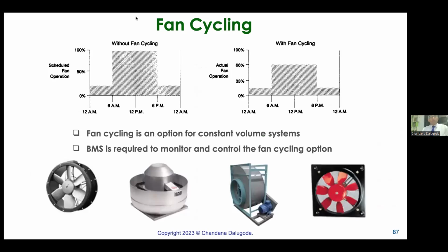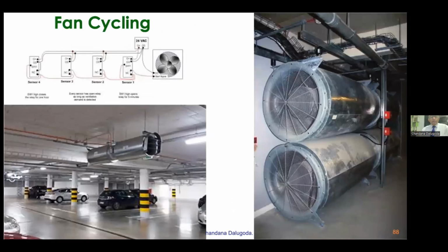Next one is fan cycling. Now fans are working continuously, at full load. That is energy killing. Say when 100% working, when it is reduced at part loads, that is fan cycling. The fans used in car parks, fan cycling is used because we need normal ventilation and a higher amount of ventilation during a fire. Usually 6 air changes for normal ventilation, 10 air changes during a fire.